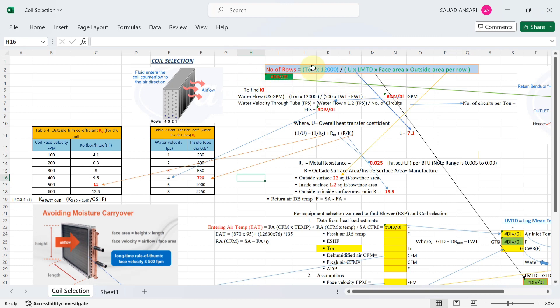Here I will show you how to calculate the number of rows of coil. The formula is: Number of rows = (TR × 12,000) / (U × LMTD × Face Area × Outside area per row), where TR is tons of refrigeration, U is the overall heat transfer coefficient, and LMTD is the log mean temperature difference.